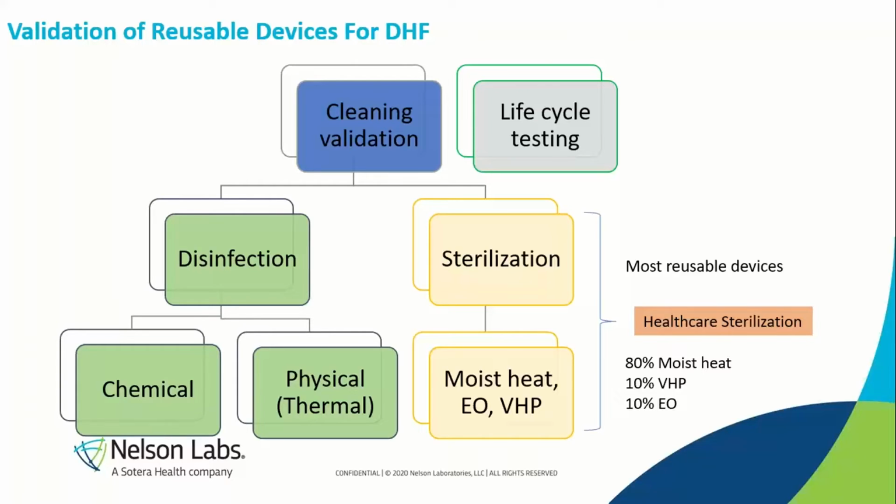Now, life cycle testing, I'll talk about a little bit, but is it a must or not? That's still a question mark. So we caution on that, but you want to think about it. Is it a requirement for a certain country or a certain continent, or do we take the safety measures? Those are the things you need to evaluate and address in a design history file, why you are not doing these tests. So the must are usually cleaning, disinfection, and sterilization.